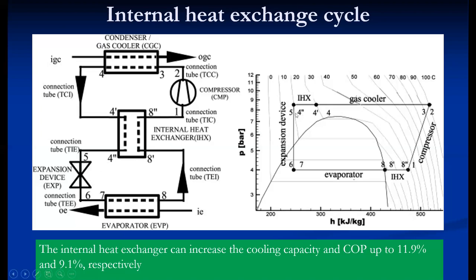Four-double-dash and five are close, and five to six is the expansion. Six and seven coincide — no losses are considered here, though practically there are some heat gain and heat loss. Seven to eight is the evaporation process. Then eight enters into the heat exchanger at eight-dash, and eight-dash to eight-double-dash is where it gains heat from the gas cooling line, which is the high pressure gas line. This is the low pressure gas line.